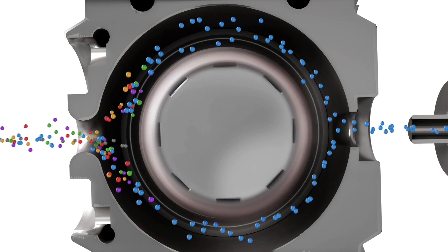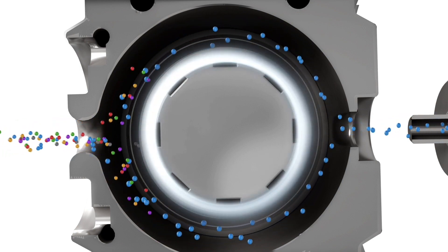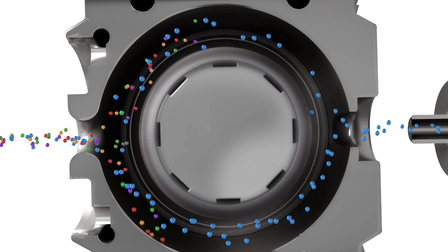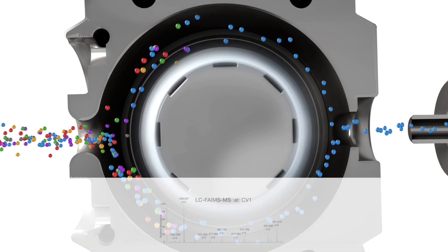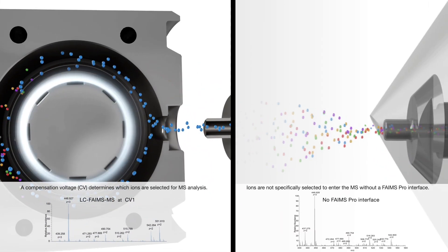To select which ion groups traverse the interface for MS analysis, a secondary DC potential, the compensation voltage or CV, is applied to the inner electrode to compensate for the displacement that changes the resulting full scan MS as compared to experiments performed without FAIMS.